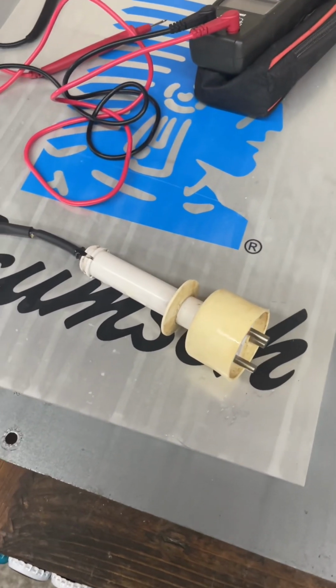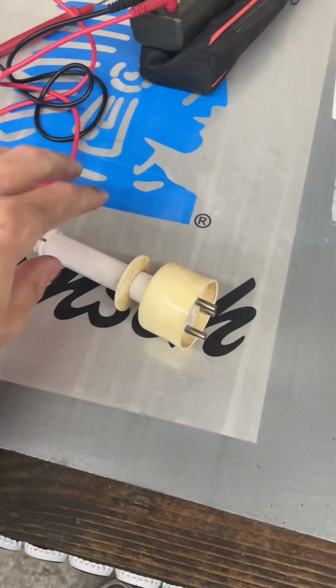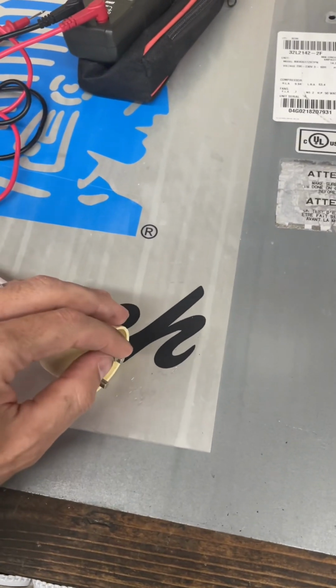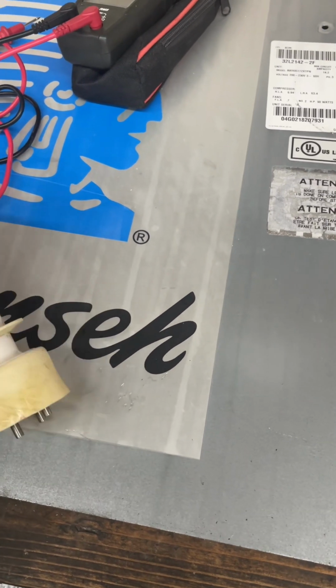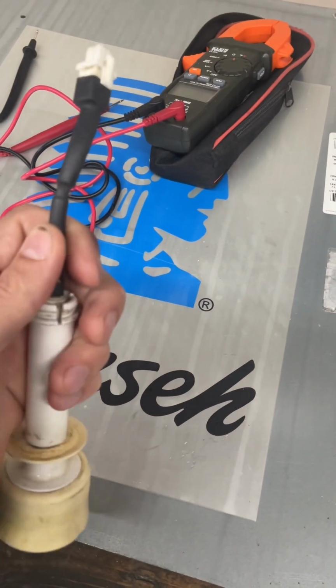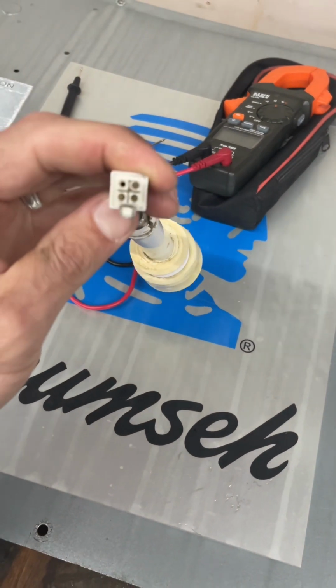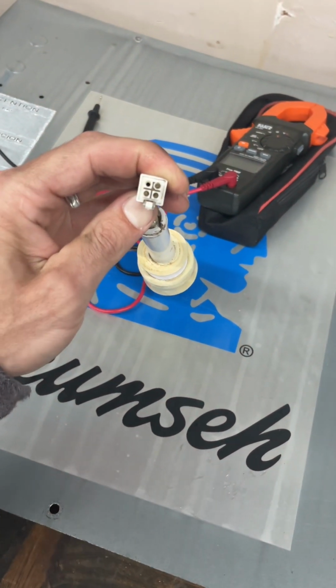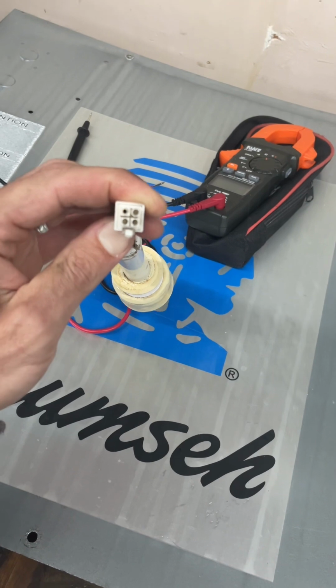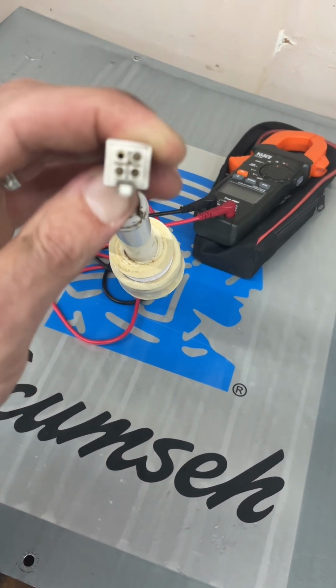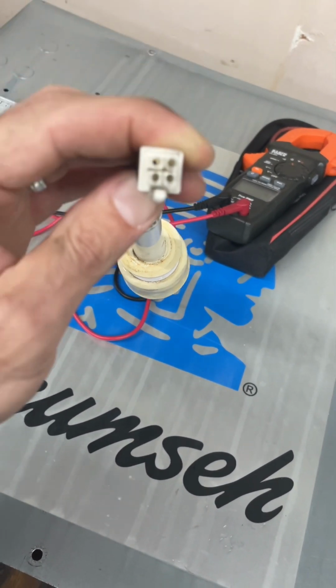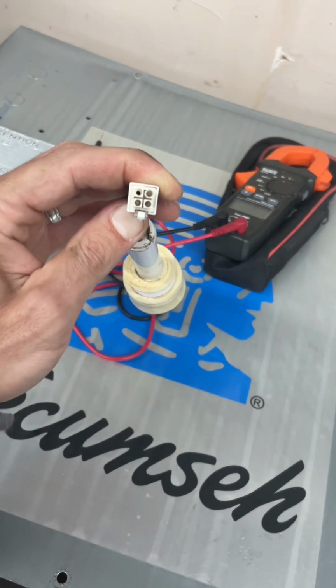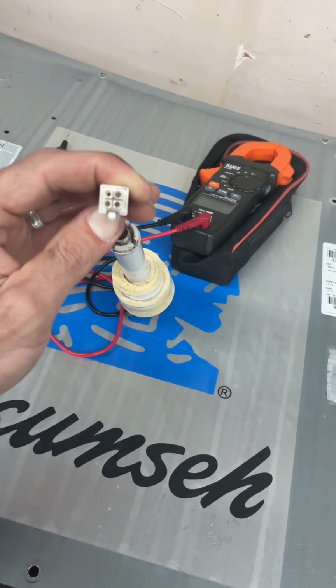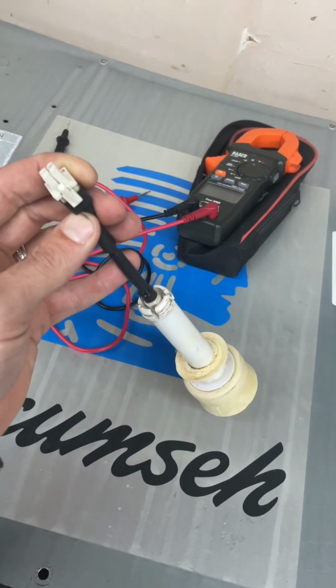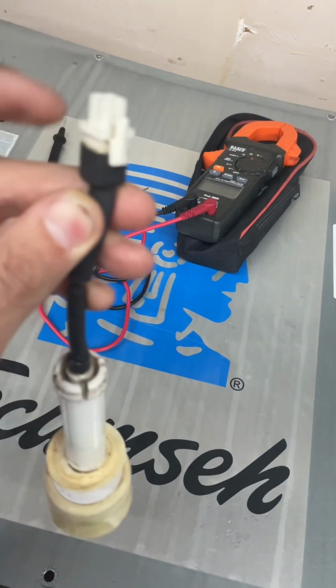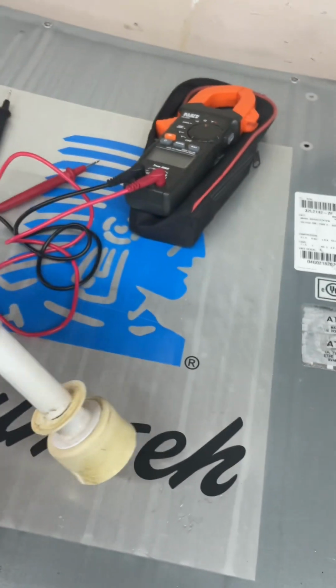First step to determine whether or not you have a bad water level probe is just check it for cleanliness. Check to see if these probes are loose. See if this connector is loose, if it wiggles up and down. You're gonna wanna check your pins. See if your pins are bent or pushed in or not there. Sorry, I can't get a good shot of that. But inside there, you just want to make sure that they all look the same, all kind of centered and not shoved back down inside of the plug.